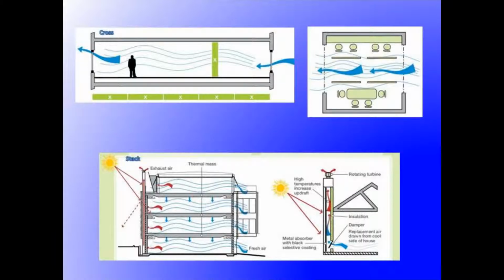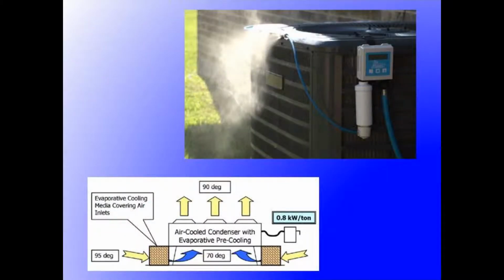Cross ventilation uses wind flow through a building. This type of ventilation is best for narrow, open-plan buildings with well-placed windows and doors. Stack ventilation draws cool air into the space from lower down to replace warmer air that naturally rises as it's warmed. Stack ventilation is generally a weaker option than cross ventilation. Cooling techniques such as pre-cooling can assist mechanical cooling systems, reducing the system's cooling load prior to occupancy. Pre-cooling lowers the heat amount released within the room during peak hours. With their occupancy patterns, churches and theaters best suit the use of pre-cooling.